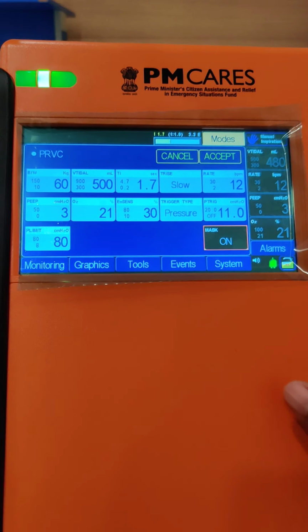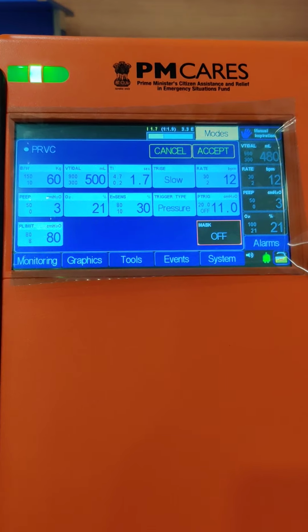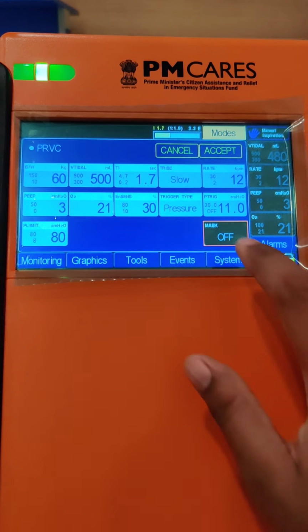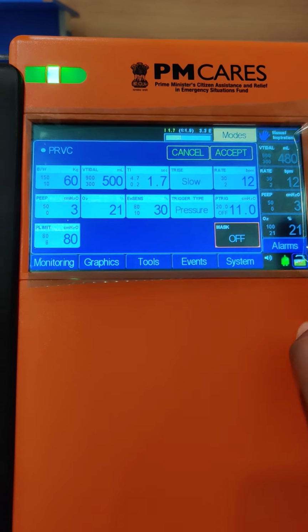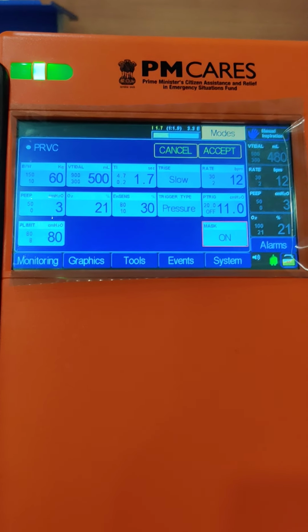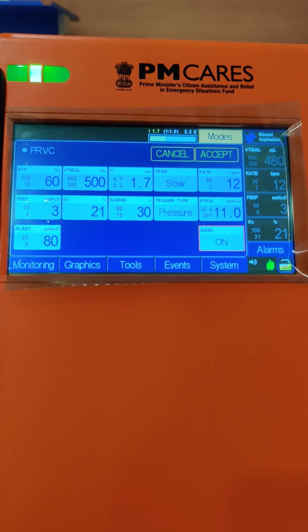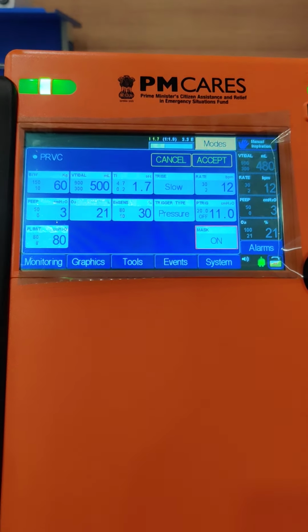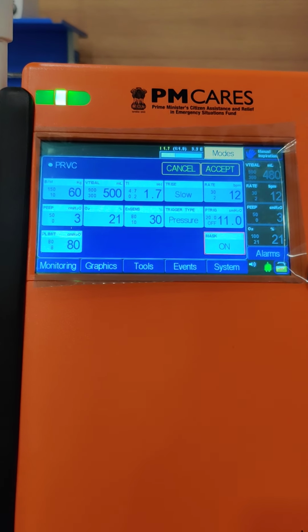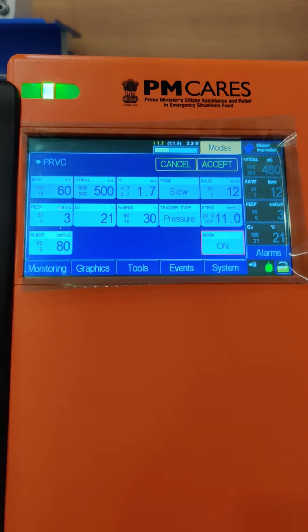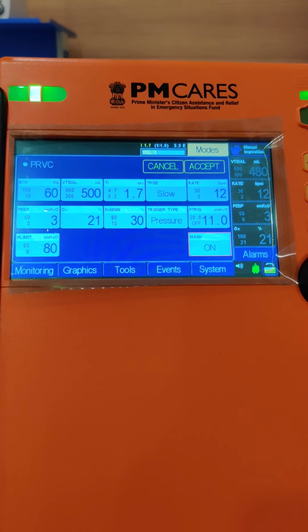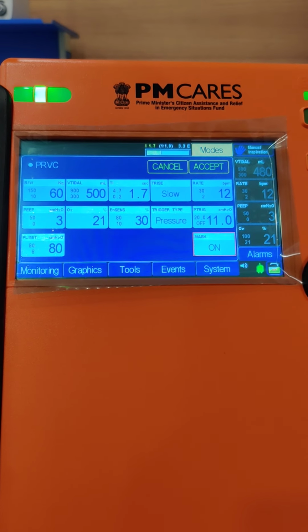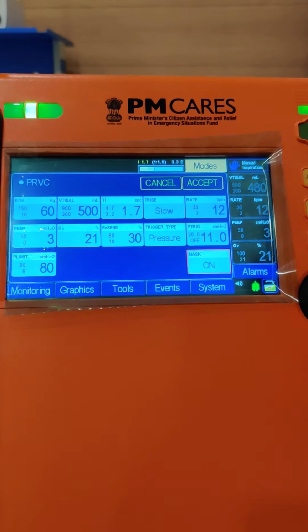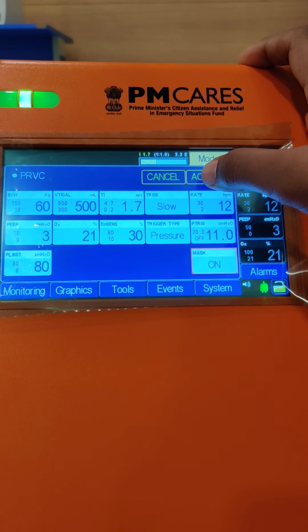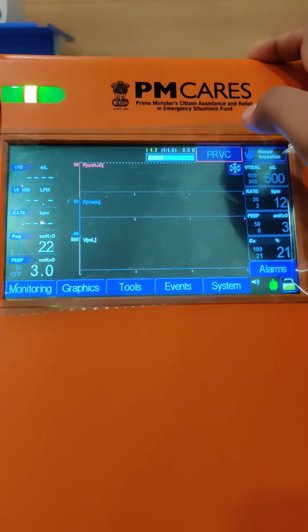If you are using it on an intubated patient, then you have to select mask off, and if you are using it on a non-intubated patient, then you have to select mask on. In mask on, it will compensate for the leakages happening from the side of the mask. Once you have changed all the parameters according to the patient's requirement and want to start the ventilation, you have to press this accept key.